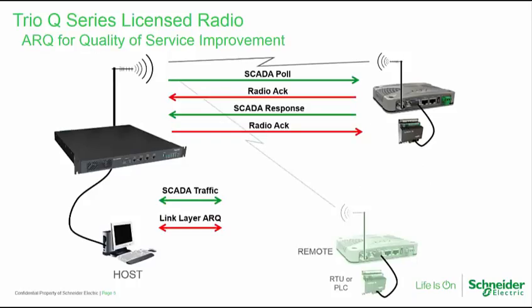A radio using dynamic mode maintains quality of service by monitoring both its measured received signal strength and any required use of automatic retry requests, also called ARQs. An ARQ is generated by a remote radio if a radio sending a message does not receive an acknowledgement, or ACK message. Retries will reduce the system's available bandwidth, but inclusion of this feature in the radio system allows the communication network to minimize issues seen by the SCADA system.